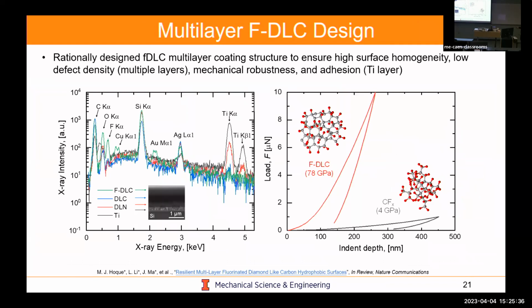And so what we do is we develop a multi-layer coating, which has different constituents. So you can look at X-ray intensity as a function of X-ray energy. This is basically an XPS scan. And this FDLC coating, which I'm showing you here, is about 2.5 microns thick, but it's got multiple layers. It's got a titanium layer for adhesion. It's got a nitrogen-rich layer for certain thermal properties, a silicon-rich layer, and then a fluorine layer that's co-deposited with DLC on top, which is about 600 nanometers thick.